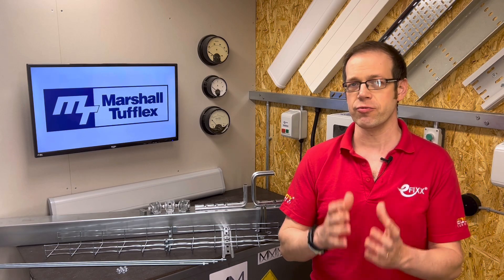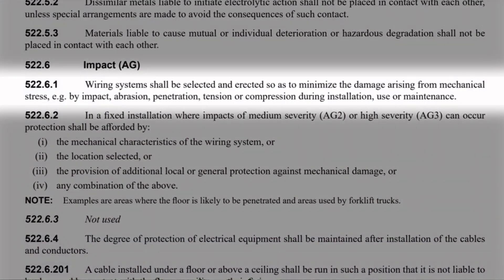So what type of containment should you be using in different environments? One of the main factors to consider is the risk of impact. Regulation 522.6.1 states that wiring systems shall be selected and erected so as to minimise the damage arising from mechanical stress — e.g. by impact, abrasion, penetration, tension or compression — during installation, use or maintenance.